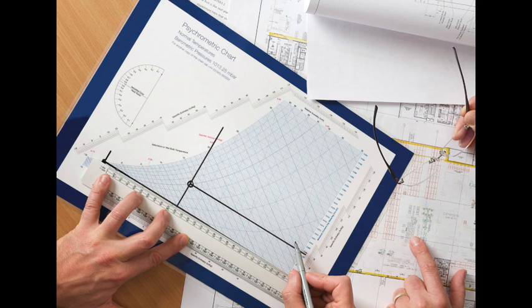A psychrometric chart shows the relationship between air temperature, relative humidity, and air's physical moisture content. These three characteristics of air are intimately linked together, and changes to one impact the other two. So by plotting our building's starting air condition and our required end condition on a psychrometric chart, we can calculate how much moisture we need to add to 1 kilo of dry air to get it from starting point A to its end point B.